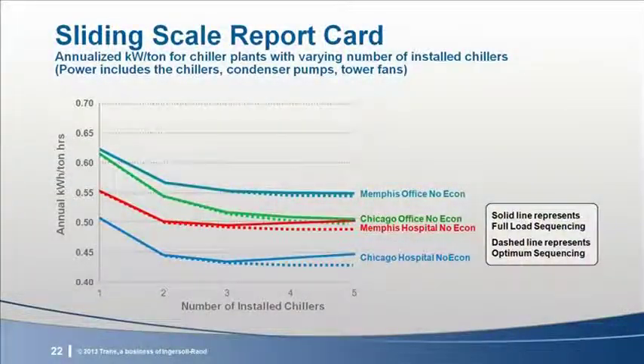This chart shows annualized kW per ton for various combinations of climate and building type. We have Memphis and Chicago, an office and a hospital. Now, adding the second chiller alone does a lot for your annualized kW per ton. But as you can see, staging chillers at full load leaves room for improvement, especially once you get to more than 3 chillers, and especially in the hospital models. The red line is a Memphis hospital without air economizer and will be discussed later by Mick.